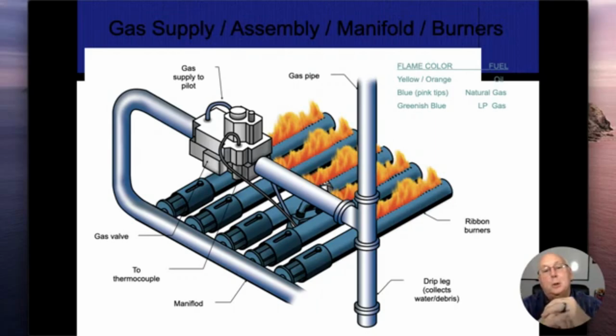Those sliding tubes and the opening as I'm coming off the manifold, those are where I draw in my combustion air. It's called Venturi tubes. As the high pressure gas shoots in there, that creates a negative pressure around it, draws in fresh air and oxygen. These ribbon burners, typically, if they're working right, are going to be putting out a nice blue flame. In the upper right corner of this slide, I would like you to look at some of those colors that are on there and just keep them in the back of your mind.